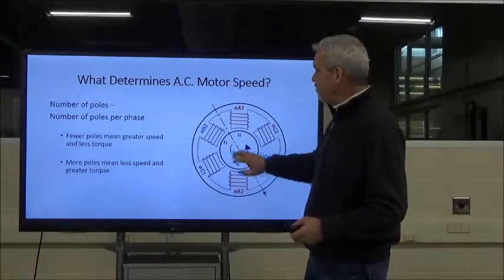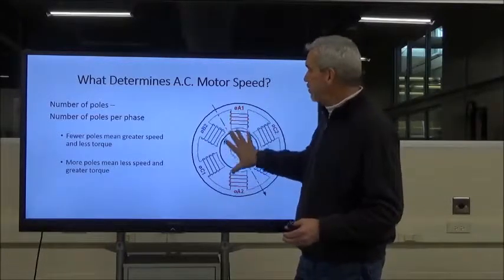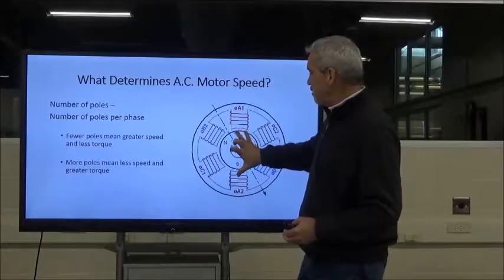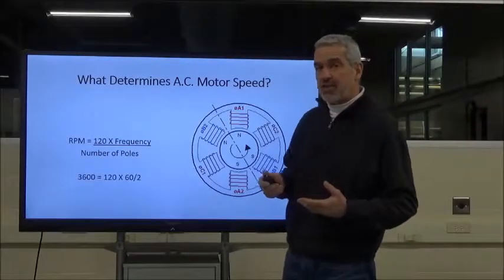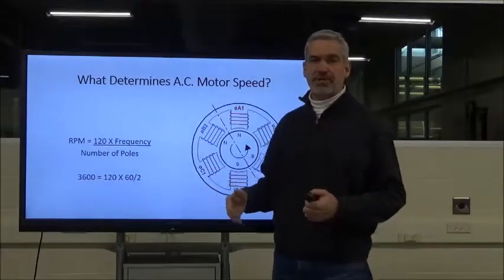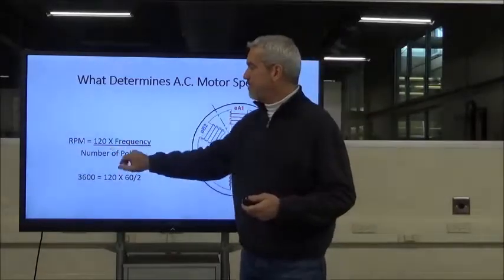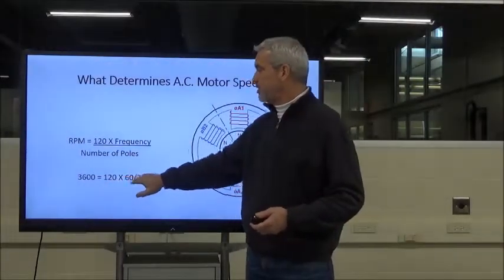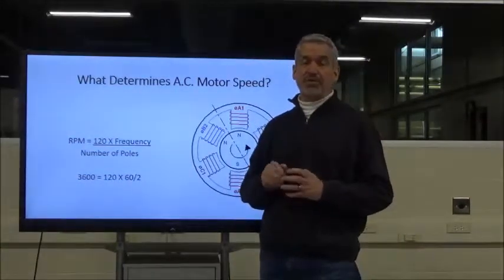This is a two-pole motor. Each phase has windings around two different poles, giving us two poles total. You can calculate RPM mathematically: RPM = 120 × frequency ÷ number of poles. With 60 hertz frequency and two poles: 120 × 60 ÷ 2 = 3,600 RPM. Notice I say theoretically — we'll get into why in just a moment.